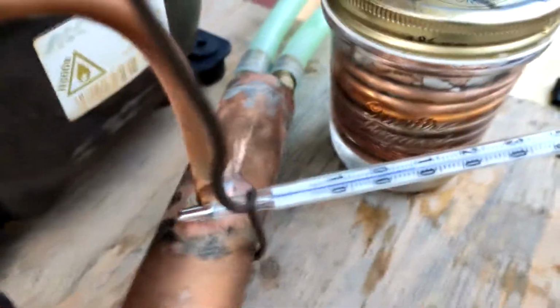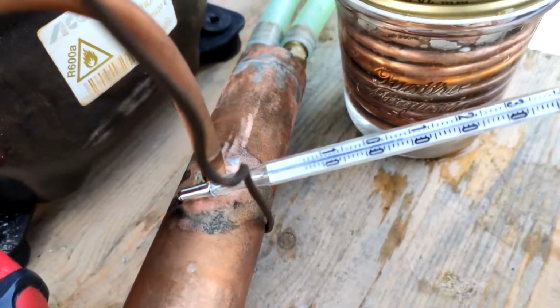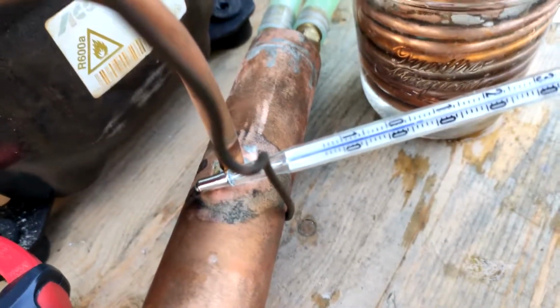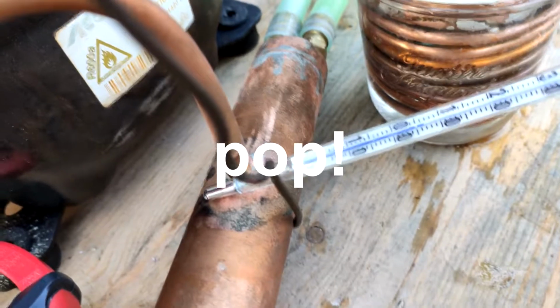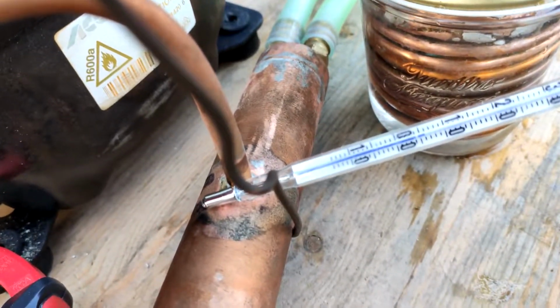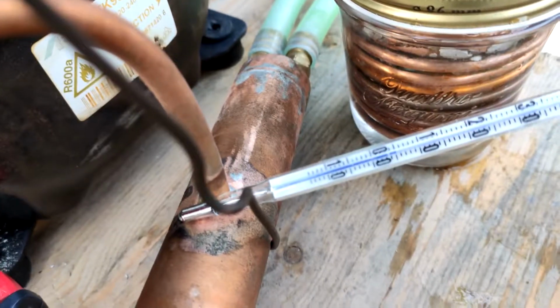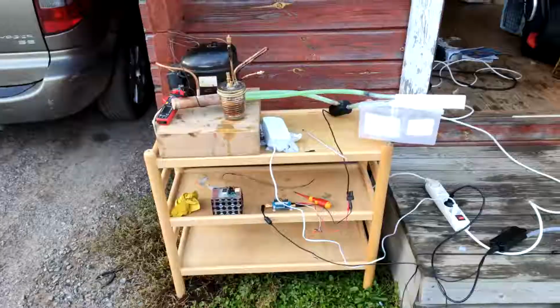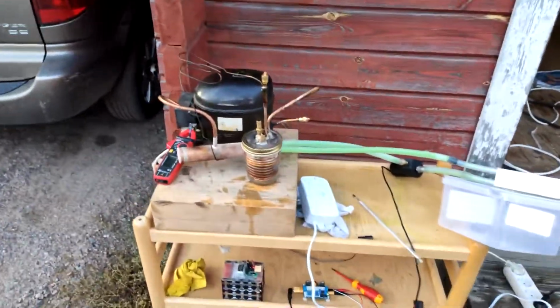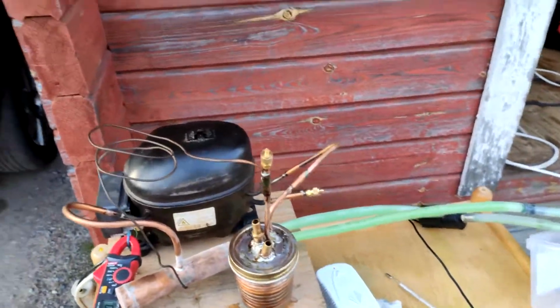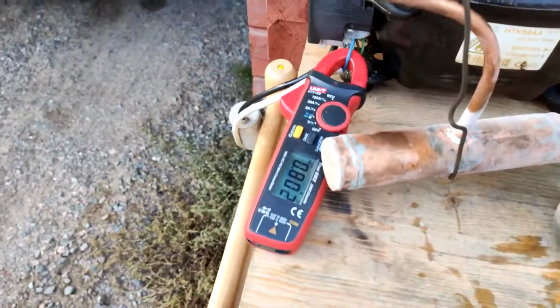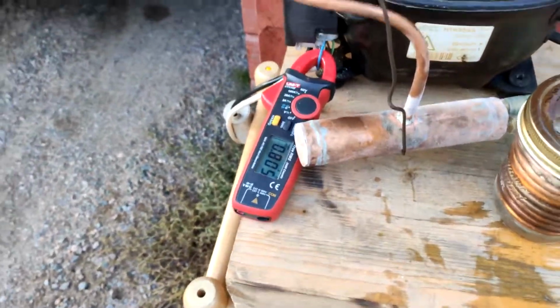And the evaporator itself is... There is actually a problem with the moisture in the refrigerant. Because the tip of the capillary tube is inside the low pressure and cold heat exchanger, the moisture in the refrigerant freezes inside the capillary tube and blocks the flow of refrigerant. That is why I can't make use of the capillary tube heat exchanger, because the moisture in the capillary tube might frost. So now it has been running for about 2 minutes. Its power draw is about 160 watts.